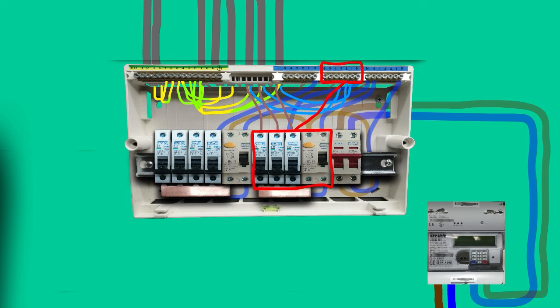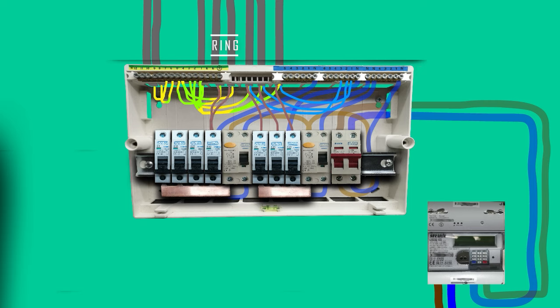The next two cables are the ring final circuit and we need to wire them to a 32A MCB. Both line conductors from these two cables go to the one MCB and both neutral conductors from these two cables go to number 1 terminal in section 3. The last three circuits are easy. Lines go to the right MCBs and neutrals go to the neutral bar terminals 2, 3 and 4 of section 3.